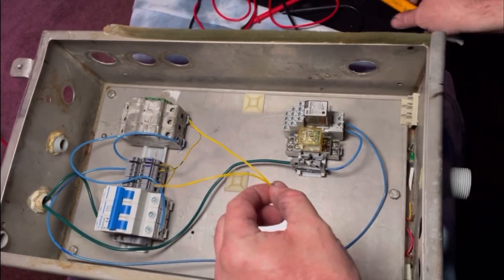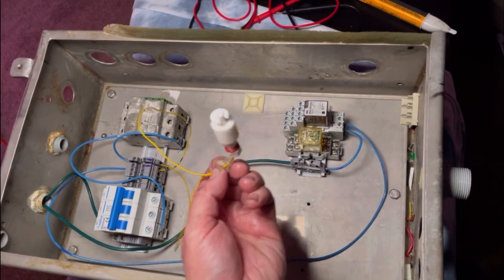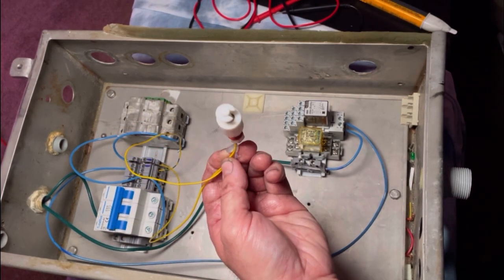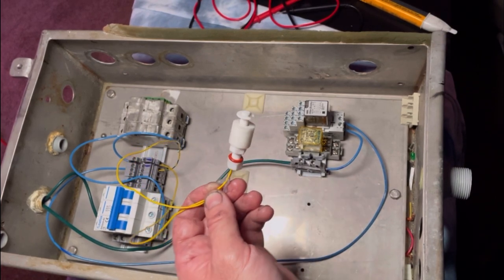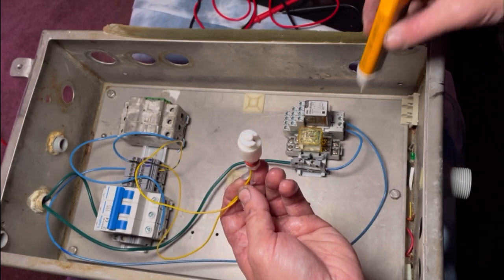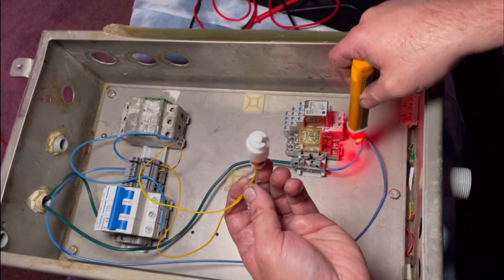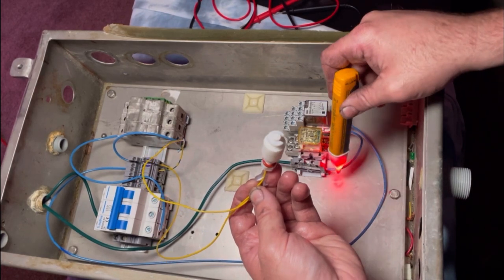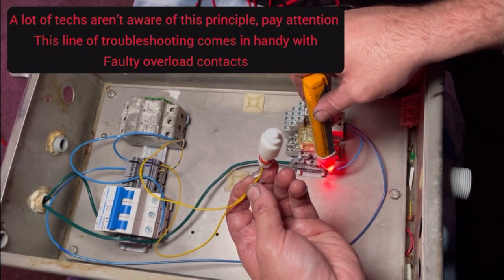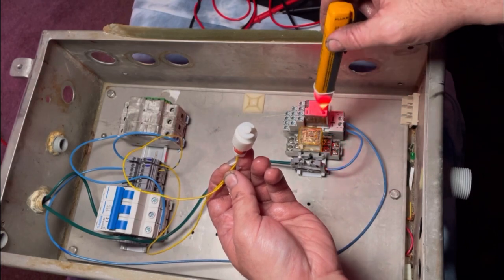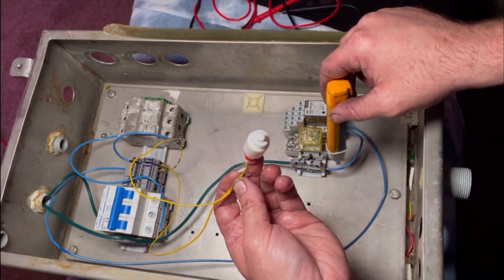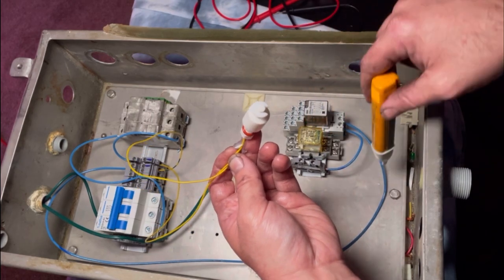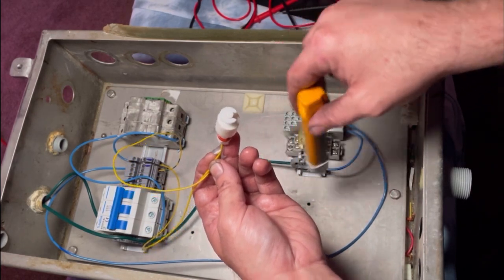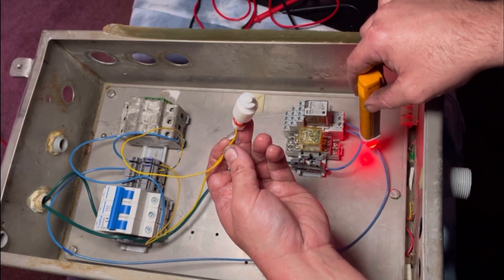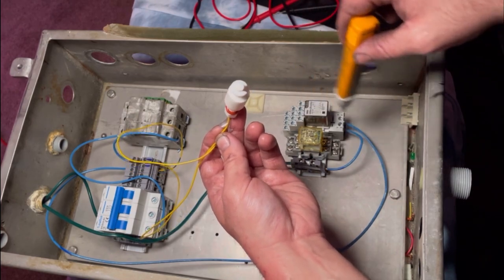All right, so I plugged in my relay, and when I flip this, the relay should click. But it's not. Aha. Oh, I have a bad connection right here. Look at that. There's a little troubleshooting tip for you. So you got your 120 going to your relay. It's actually going through that coil. So you still have voltage coming out of it, but the power is not being consumed. There's zero current on this line. Once I make this connection to neutral better, like get a good connection, you'll have voltage going in, no voltage going out, and you'll actually have power running through that line.